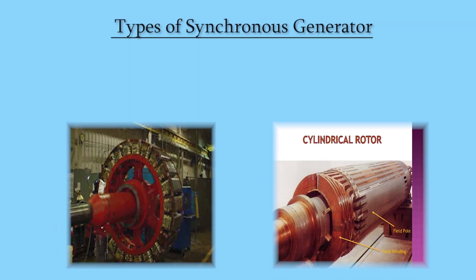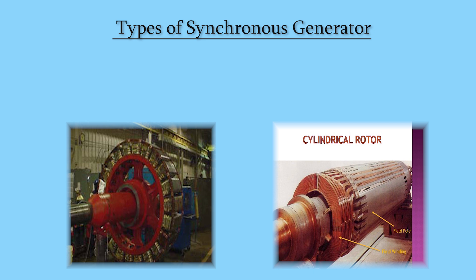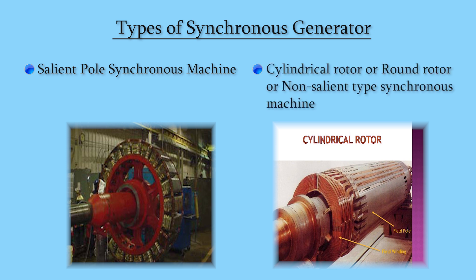There are two types of synchronous generators. In the salient pole synchronous machine, the poles are projected out of the surface with the winding placed in between. In the cylindrical rotor, you have a smooth surface. Salient pole synchronous machines are normally used for low speed operation, whereas cylindrical rotor machines are normally employed for high speed.